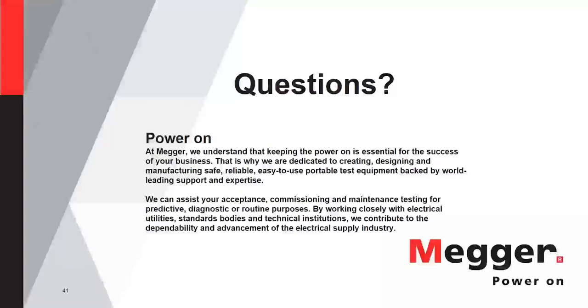Okay, I can start answering the question, and probably Andy can help me also. If you have been doing all of this testing, definitely you have been doing things correctly. One thing that I didn't mention at the beginning is that batteries have a definite lifetime span, so they will die, and usually they are designed for 20 years or 10 years, and battery temperature conditions will affect how the life of the battery will behave. But if you have been keeping them in very good condition, and all of the measurements with BITE are not showing any deviation, you might still have a good battery, but anyway, they will die, and 18 years old is pretty close to the end of the life of a battery. I don't know, Andy, if you have something to add there.